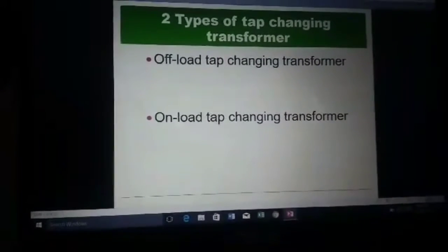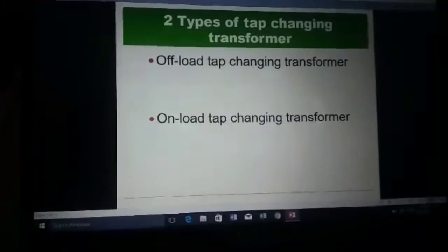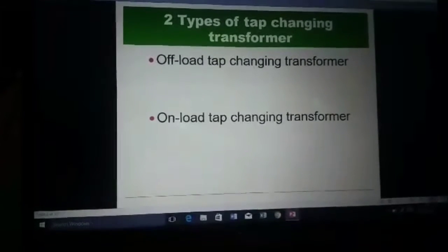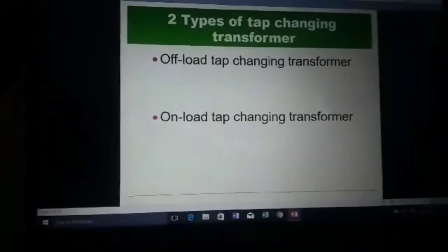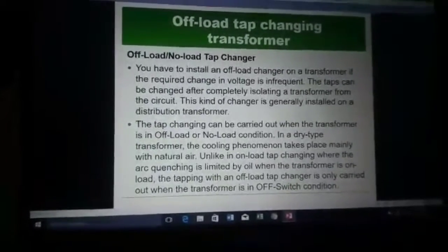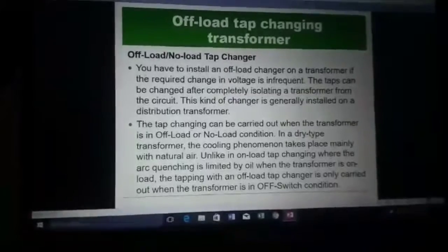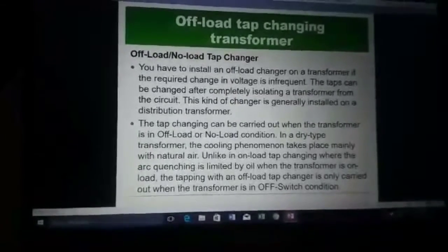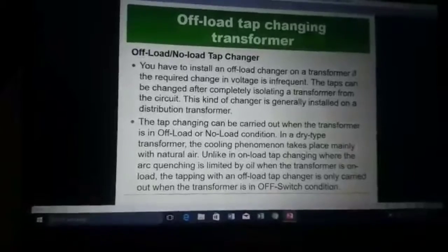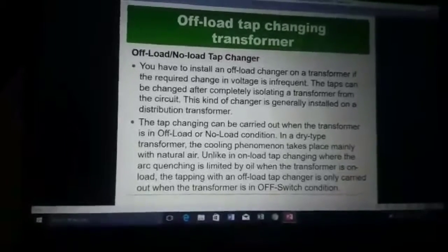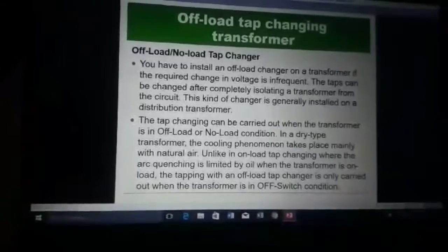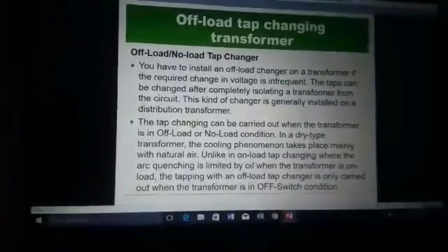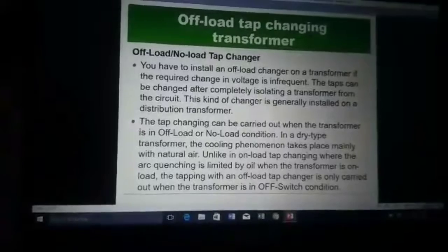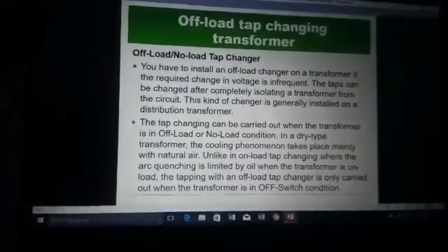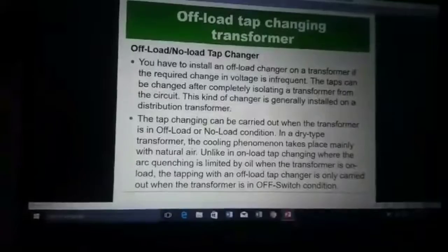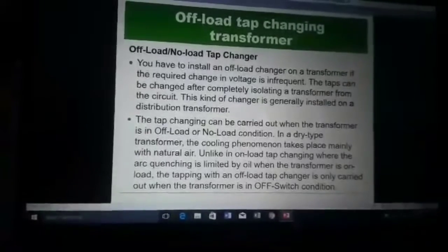So we have two types of tap changing transformer. First is offload tap changing transformer and the other one is onload tap changing transformer. You install an offload changer on a transformer if the required change in voltage is infrequent. The taps can be changed after completely isolating a transformer from the circuit. This kind of changer is generally installed on distribution transformers. The tap changing can be carried out when the transformer is in offload or no load condition.